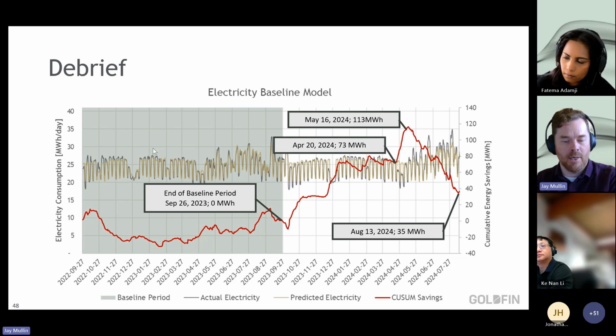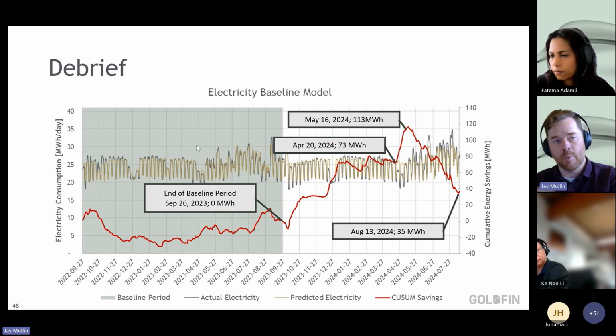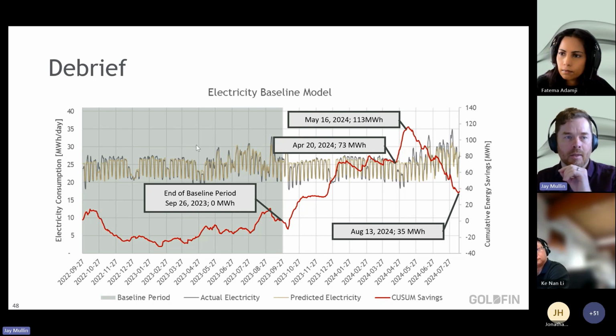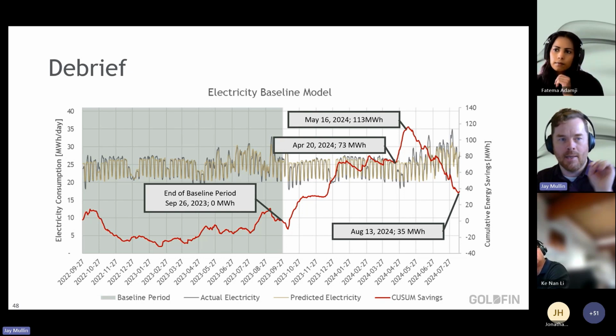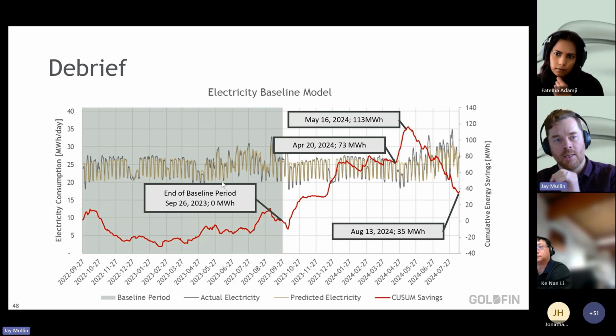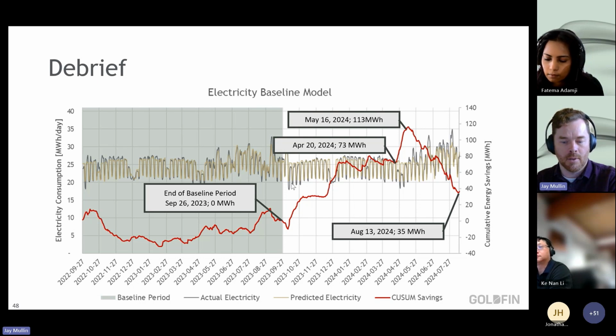It gets calibrated through the baseline period, running a regression analysis that produces an equation: for every cooling degree day add this much energy, for every heating degree day add this much energy, if it's a weekend subtract this much, if it's a Christmas break subtract this much from what it otherwise would have gotten. That's how it develops the prediction and normalizes for changing situations.